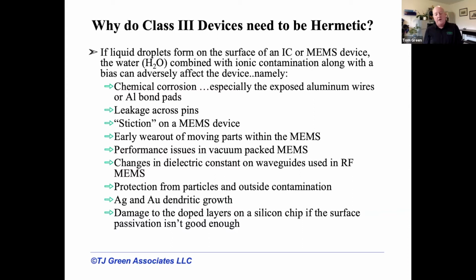So, one of the most susceptible parts, if it's a hybrid, a lot of these implants are basically hybrids. They're chip and wire, bare die, with passive components, maybe a double-sided board. But the bond pads on an aluminum chip, where it's a typical silicon IC, are very sensitive to moisture. And if you have any kind of moisture on the surface of an integrated circuit, you could have leakage, you could have surface conduction, you could have electrical issues.